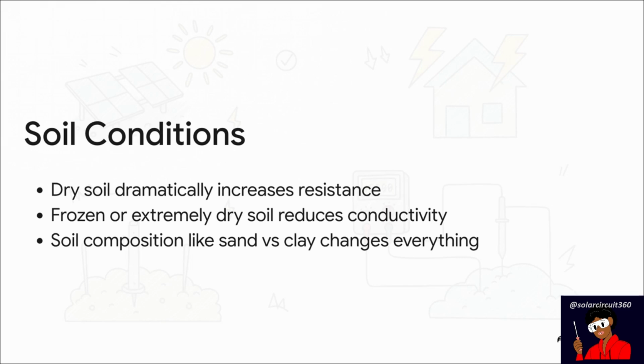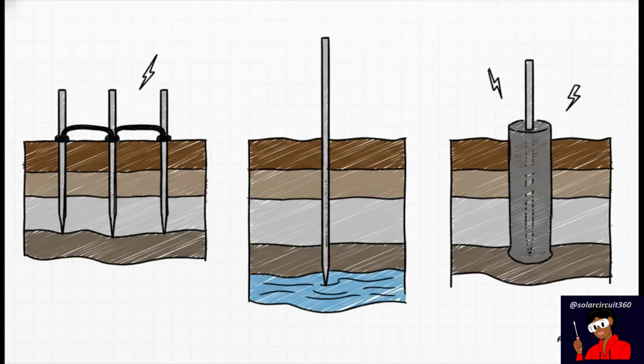Similarly, when winter hits and the ground freezes solid, the soil's conductivity plummets, causing your resistance to spike. Even the composition itself, like loose sand versus dense clay, changes the performance entirely. So what happens when nature works against you? Well, this is where professional adjustments come into play. If a single, standard ground rod just isn't cutting it in dry sand or freezing conditions, professionals don't just shrug and walk away. They adapt.